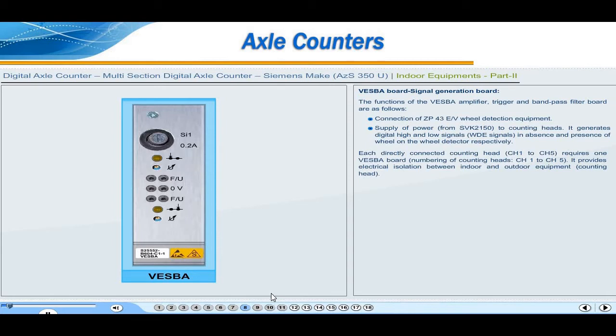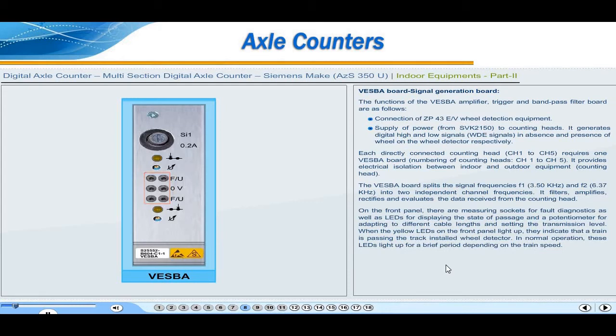Each directly connected counting head, that is counting head 1 to counting head 5, requires one VESBA board, that is numbering of counting heads 1 to 5. It provides electrical isolation between indoor and outdoor equipment, that is counting head. The VESBA board splits the signal frequencies F1, that is 3.5 kHz, and F2, that is 6.37 kHz, into two independent channel frequencies. It filters, amplifies, rectifies, and evaluates the data received from the counting head. On the front panel, there are measuring sockets for fault diagnostics as well as LEDs for displaying the state of passage and a potentiometer for adapting to different cable lengths and setting the transmission level.